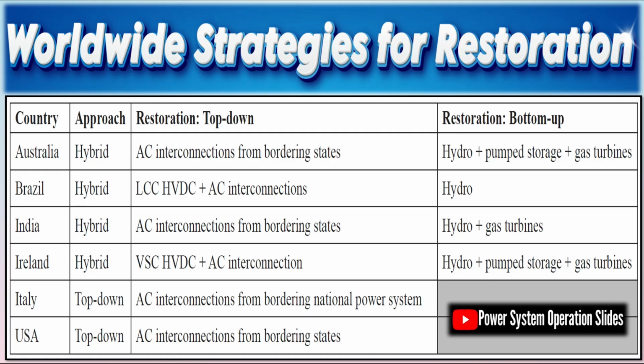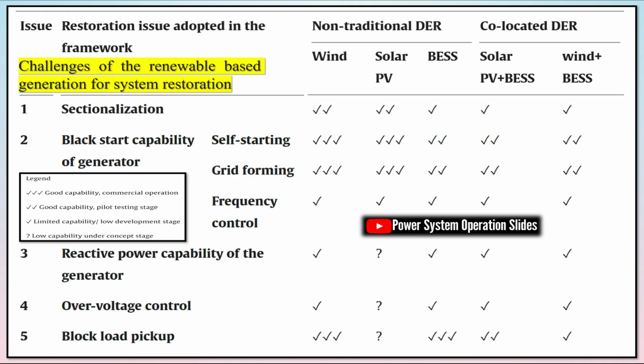As the energy landscape evolves, future power systems are expected to become more dynamic and less inherently stable unless new measures are adopted. Key challenges include reduced frequency stability due to declining synchronous inertia, volatile short-circuit power levels across the network, and limited and dispersed voltage control resources. Currently, residential units offer minimal support for ancillary services like voltage regulation or balancing, and they are rarely redispatched for congestion management. Most residential technologies also lack restoration capabilities and remain largely unobservable or uncontrollable by TSOs, both of which are essential for coordinated recovery.